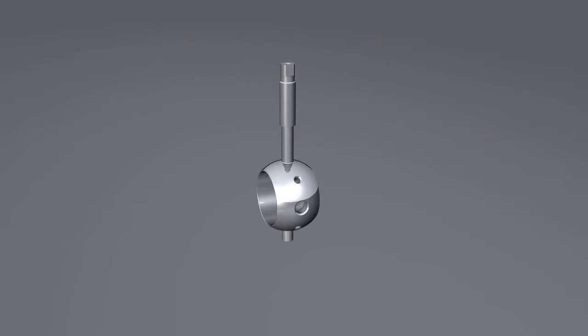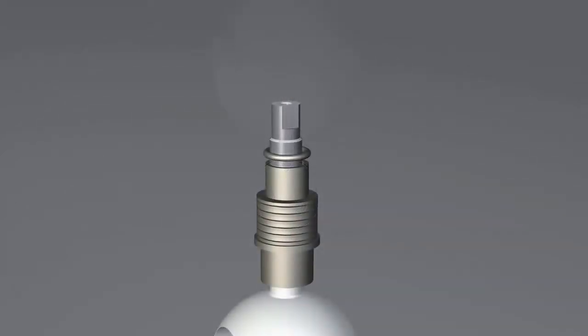The ball in a two-piece traditional ball and stem design can float downstream under pressure, imparting increased force on the seat to enhance the inline seal. Unlike the XLB, in other one-piece designs such movement of the ball can lead to side loading of the packing, unless the valve is mechanically held in place to prevent the movement.